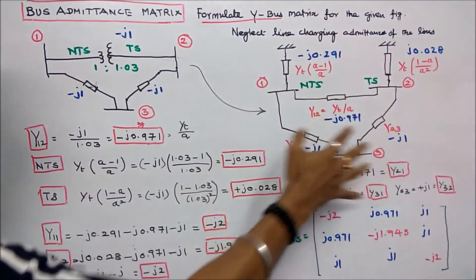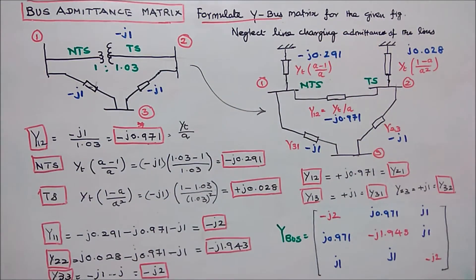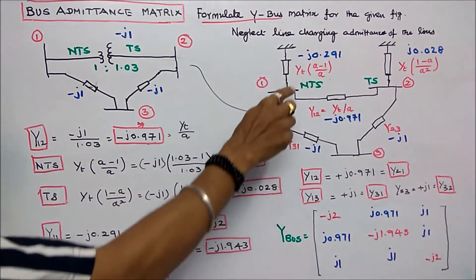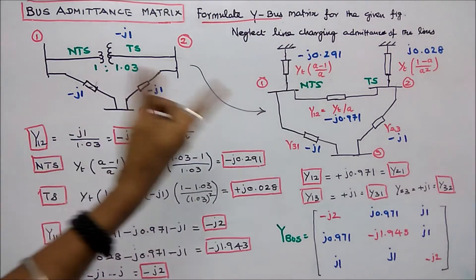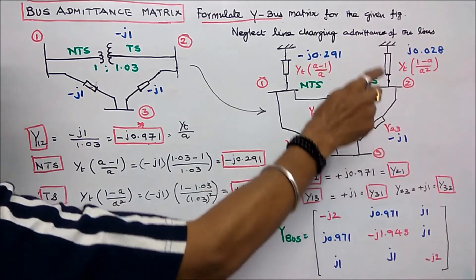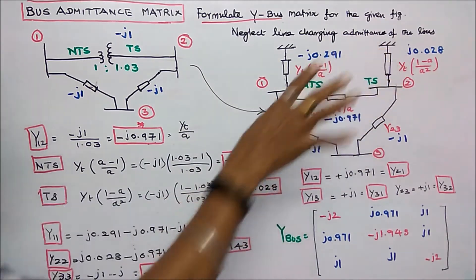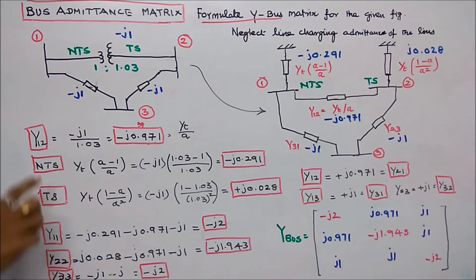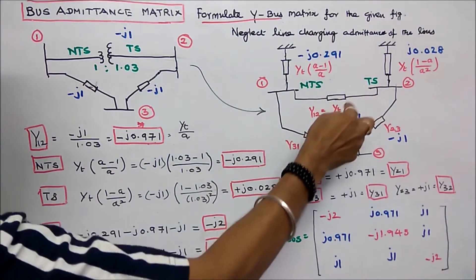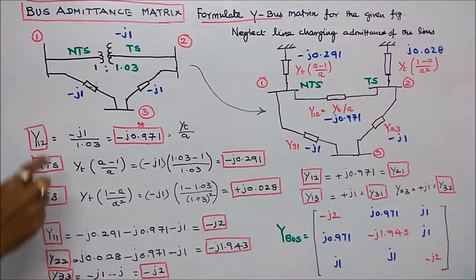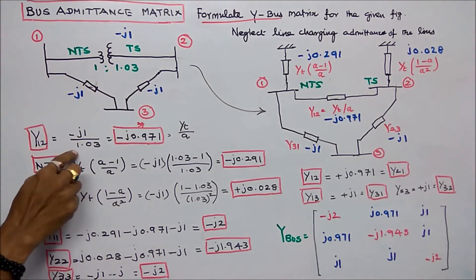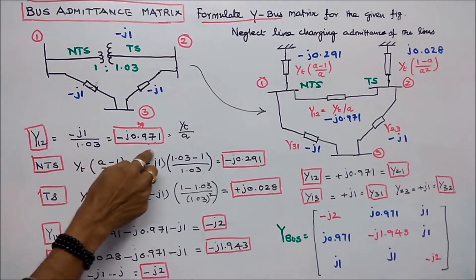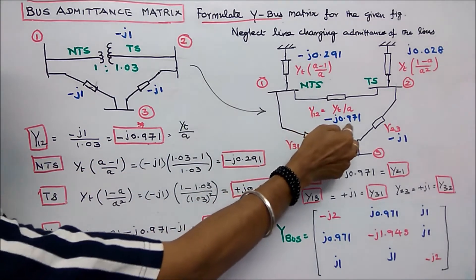Second step: we have to draw the equivalent circuit. On the non-tap-setting side, the line charging admittance is Yt times (A minus 1) divided by A, where Yt equals minus J1. On the tap-setting side, it is Yt times (1 minus A) divided by A squared. So Y12 equals Yt divided by A, which is minus J1 divided by 1.03, equal to minus J0.971.